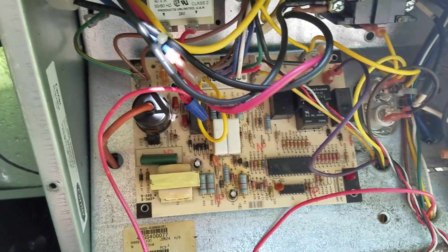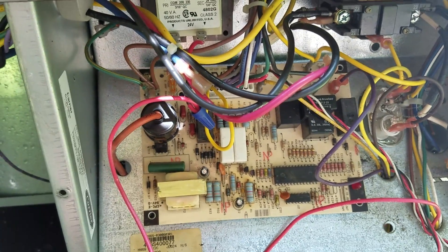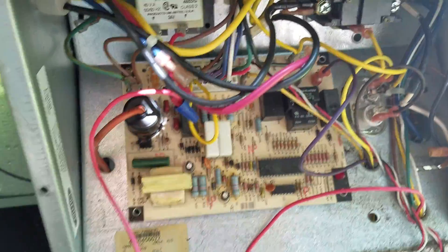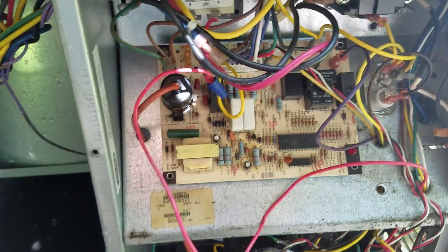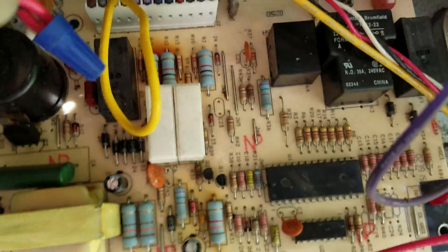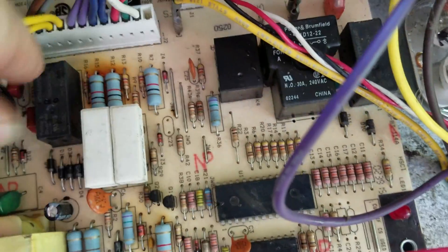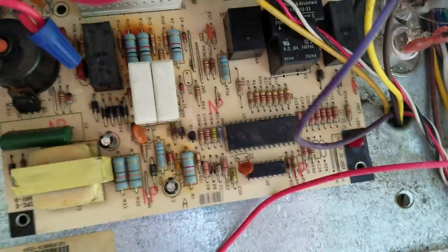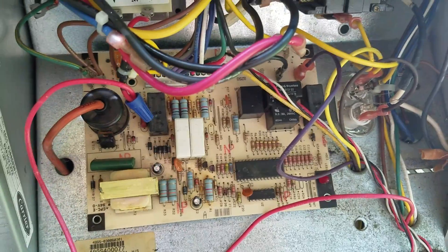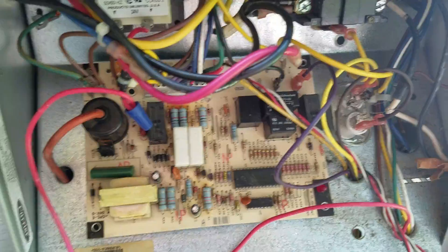In this video we're going to show you something that we only want to do in case of emergency. This particular case is a Carrier gas pack 48GS. Everyone's out of them — they have the problem with their resistors here burning up, and that's a typical problem on most of these. It's extremely hot this week so I'm not going to leave my customer with no air conditioning.